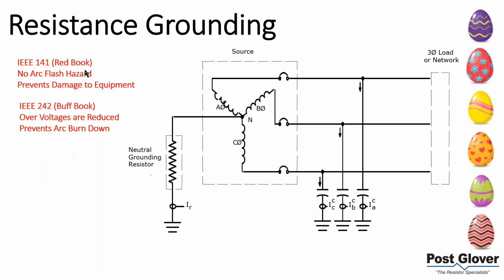In terms of the IEEE Red Book, it talks about how there's no arc flash hazard. That's a little bit too short of an answer. There's no arc flash hazard for ground faults. About 98% of all your faults are line to ground, roughly, give or take a couple. So for those faults, you have no arc flash hazard. There's not enough voltage to create that arc. Then you also drastically lower your current. Once again, you're engineering that. Essentially, it takes the best of solid grounded and ungrounded systems and gets rid of the bad stuff. That's how I like to think about it. So overvoltages are reduced, really talking about straight ground currents.